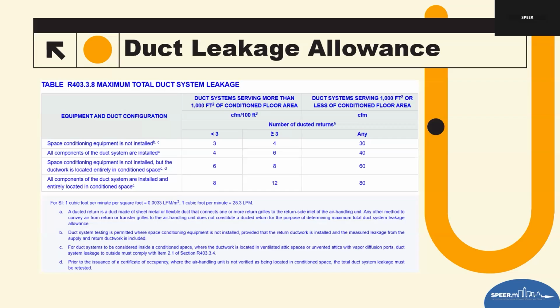So if we have one that has more than 3 returns, and all systems and air handlers are installed, and it is totally 100% inside conditioned space, now we have an allowance as high as 12 CFM per 100 square feet. We haven't seen that in quite some time. It used to be 8 for ducts in conditioned space if all equipment is installed, but now it says if that's less than 3 returns, 8, and anything more than 3 returns, we've gone up to 12.